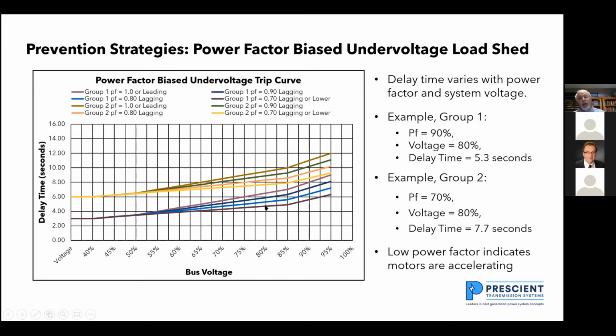If I've got a poorer power factor, what that's telling me is a lot of motors are reaccelerating. And if all the motors are reaccelerating simultaneously, that's a huge VAR demand on the system. So rather than taking that huge VAR demand, I should start shedding load, and that'll give me step increases in voltage and allow the voltage to recover quickly.